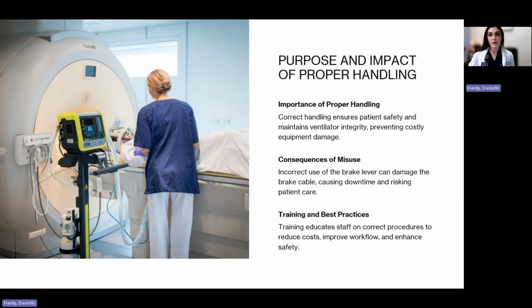So proper handling of the Hamilton MR1 trolley system is critical for ensuring patient safety and maintaining the integrity of the ventilator equipment. Over the past year, we have 17 documented incidents where incorrect handling led to brake cable damage, rendering trolley and ventilator unusable. These failures not only resulted in costly repairs, but also create significant downtime, which can compromise patient care during critical moments, and then also it makes everyone a little bit upset.